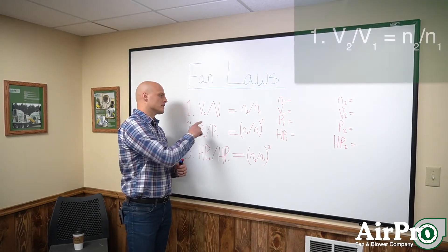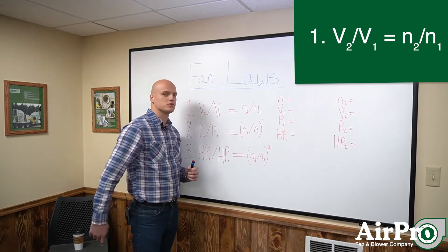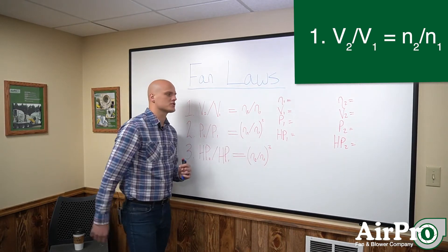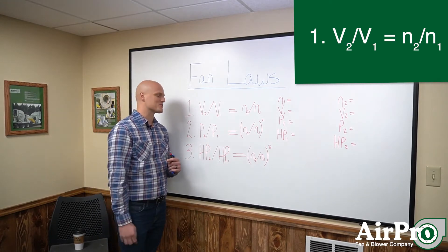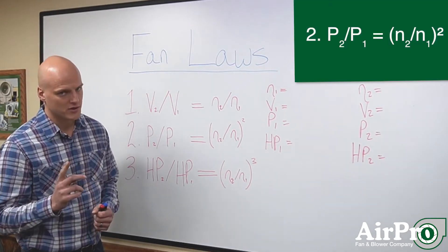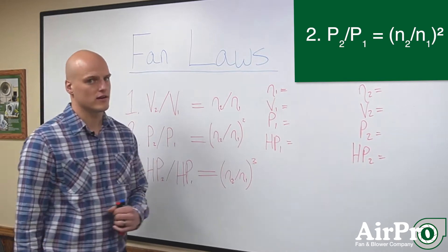The first law is that your volume is going to change proportional to your speed change. So V2 over V1 equals n2 over n1. The second law is that your pressure is actually going to change proportional with the square of the speed change.